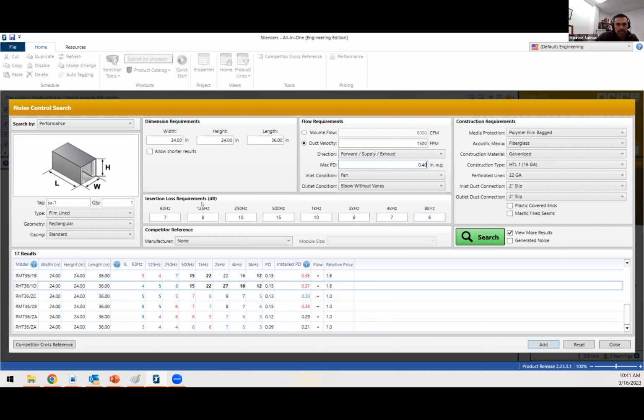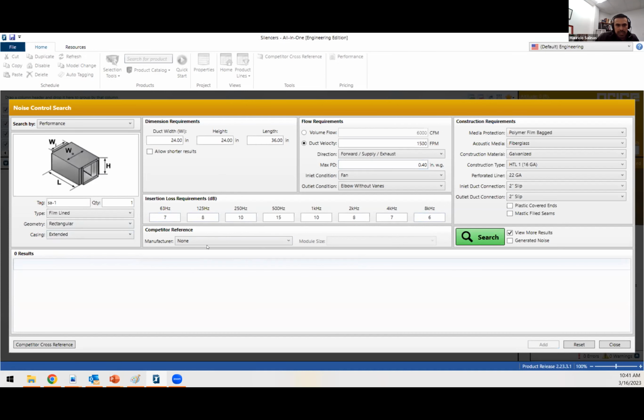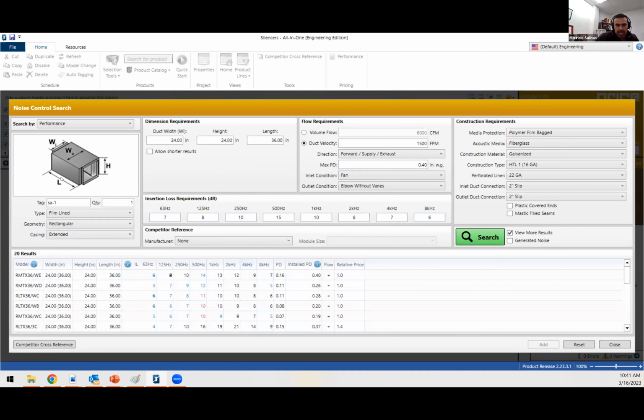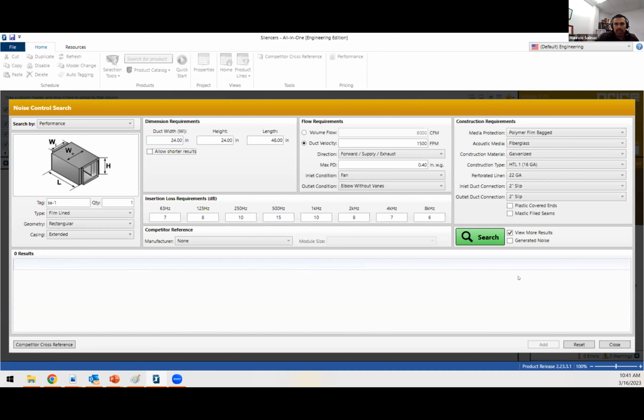The lower octave bands, the lower frequencies, are the hardest to attenuate due to the size of their wavelength. So if you want to achieve a bit more points, you might want to try an extended casing silencer, which adds wings, so 6-inch wings to your unit. And if you look at that, at a 0.4 installed pressure drop, you are meeting most of the requirements that you need. Now, that's one way to boost performance for a silencer. There is another way that has less of an impact on pressure drop, which is making it longer.